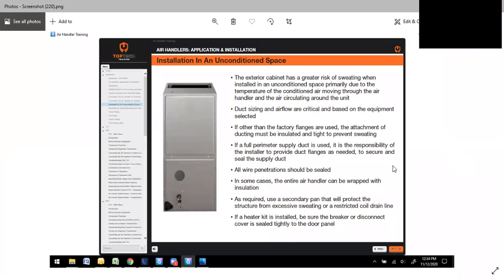If a full perimeter supply duct is used, it's the responsibility of the installer to provide duct flanges as needed to secure and seal the duct. All wire penetrations to be sealed. In some cases, the entire air handler can be wrapped with insulation. As required, use a secondary drain pan that will protect the structure from excessive sweating or restricted coil drain. If a heater kit is installed, be sure the breaker or disconnect cover is tightly sealed to the door panel.